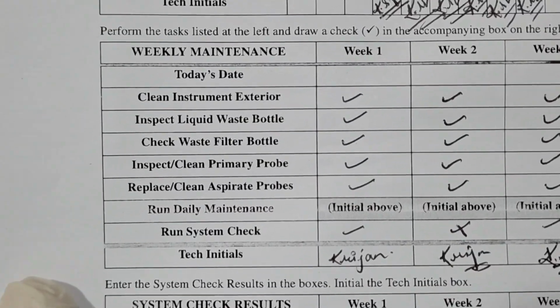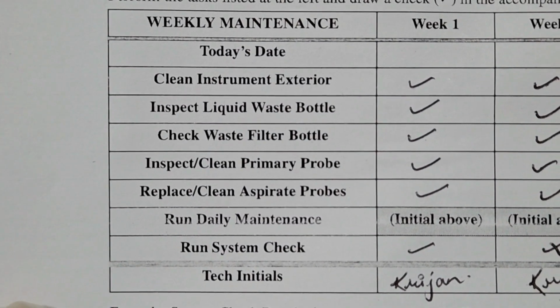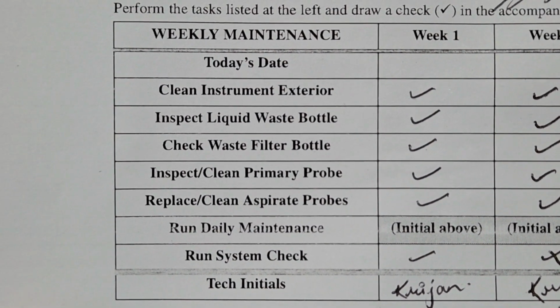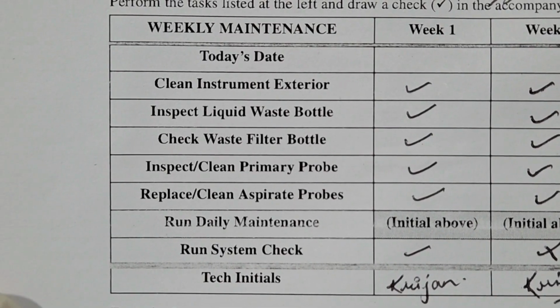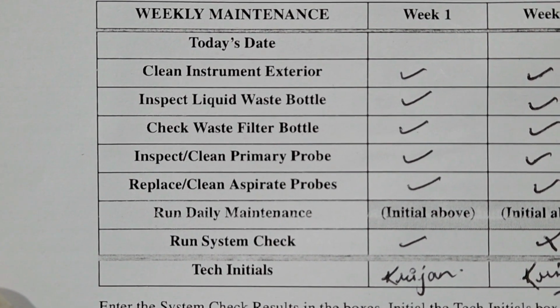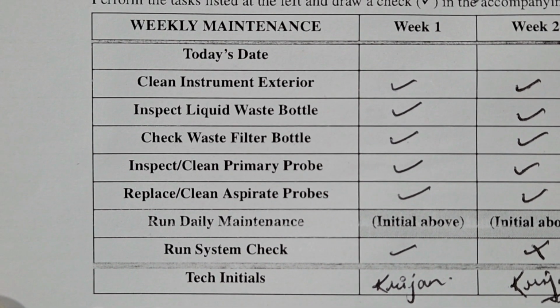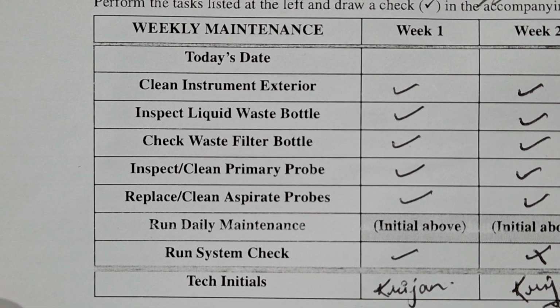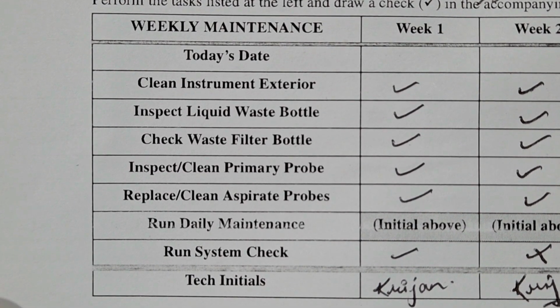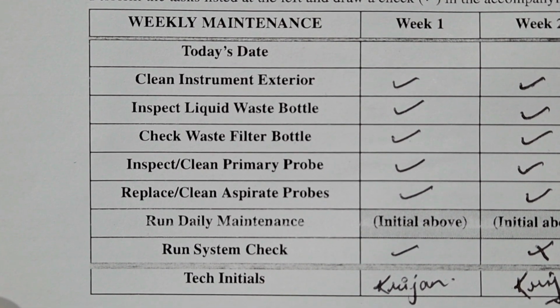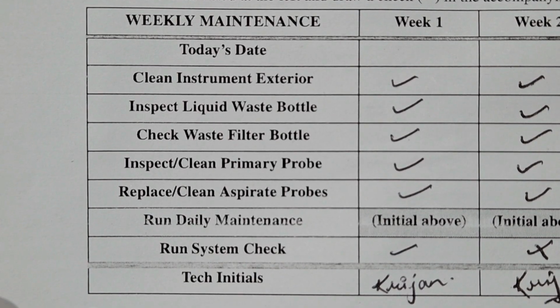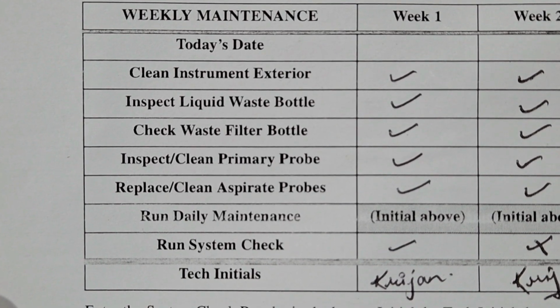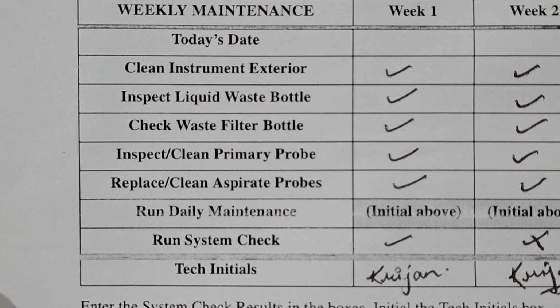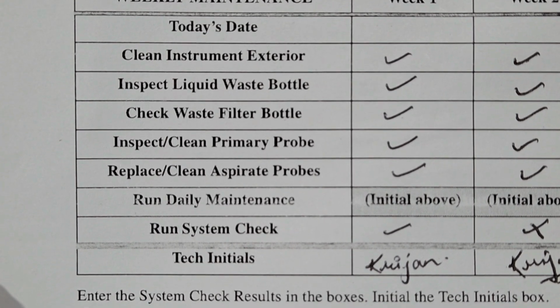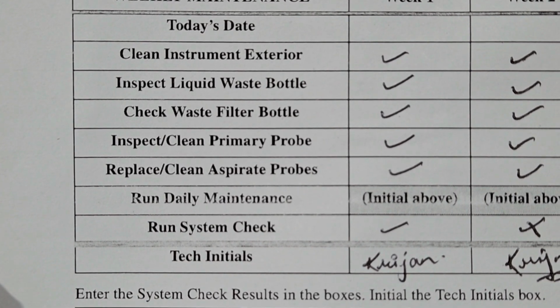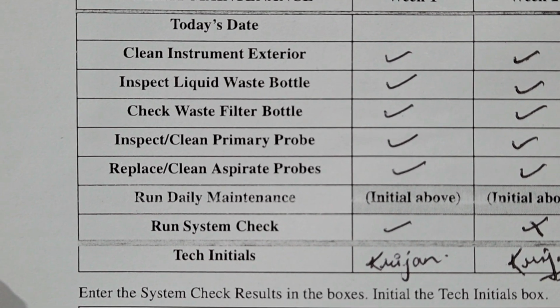As you can see here, our weekly maintenance checklist includes a few steps such as cleaning the exterior surface of the instrument, which means cleaning the exterior part of the analyzer, inspecting the liquid waste bottle for any leakage or overflow, checking the condition of the waste filter bottle, inspecting or cleaning the primary probe, replacing and cleaning the aspiration probes. Finally, as usual, performing the daily maintenance routine and running a system check to confirm that everything is functioning optimally.